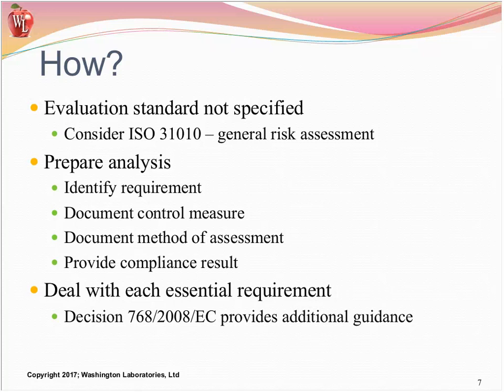Since obviously if you're in this technology realm, you're not within the harmonized standards, so it's indicated you will need to use a notified body to obtain your compliance, shall we say, or your approval. So you're going to be explaining that to them. That may take on some additional justification and support. Dealing with these advances is always a kind of tricky situation.